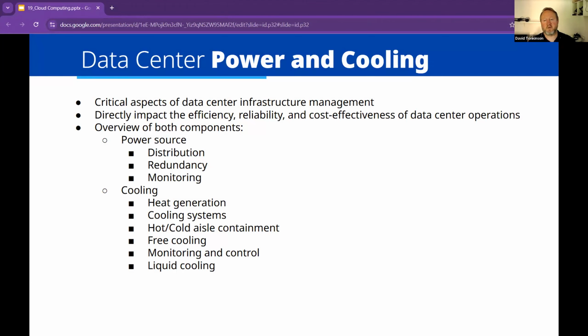I talked about the power distribution units that run down the side of the systems. Each one of those, you can have smart ones. So I can monitor the power that each plug is actually taking out of that system to give me details in terms of what server is running hardest, what server is burning the most power, what's most cost effective. And it can also tell me when it fails, which is great.